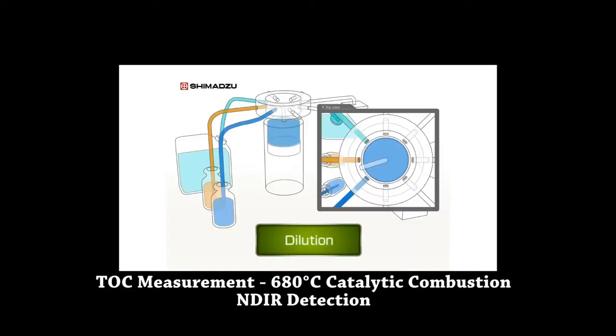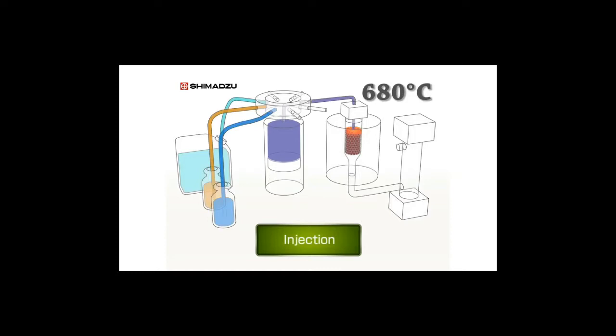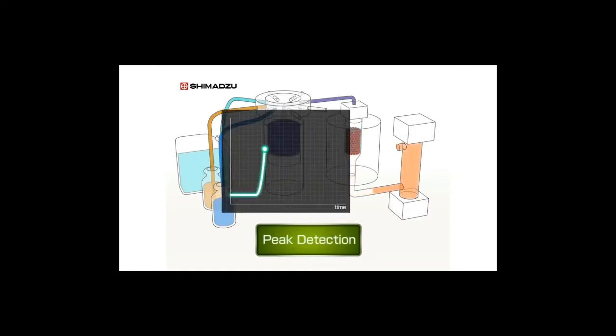In the APHA 5310B method, the water sample is first diluted, then acidified and sparged. After sparging, inorganic carbon is removed from total carbon. The sample is then injected into a combustion oven and heated at 680°C with a catalyst. The sample is oxidized, liberating carbon dioxide, which is measured using an NDIR detector to obtain the TOC value.